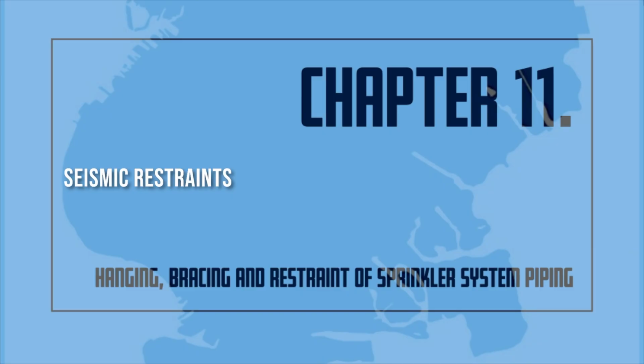Piping shall be protected against damage where subject to earthquakes by the use of flexible couplings for piping 2.5 inch and larger. Flexible connection shall also be provided at building expansion joints and within 24 inches of top and bottom of the piping dropping down to in-rack sprinklers and mezzanines regardless of pipe size.